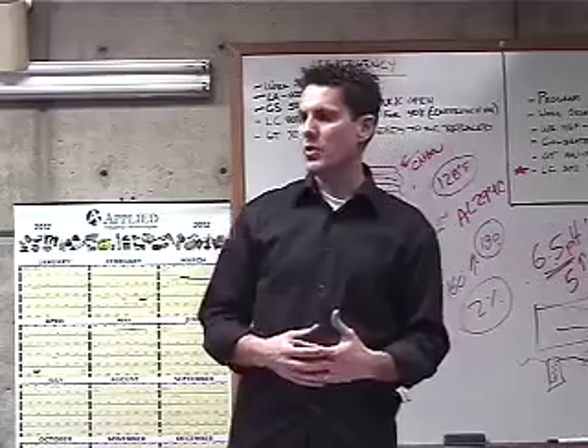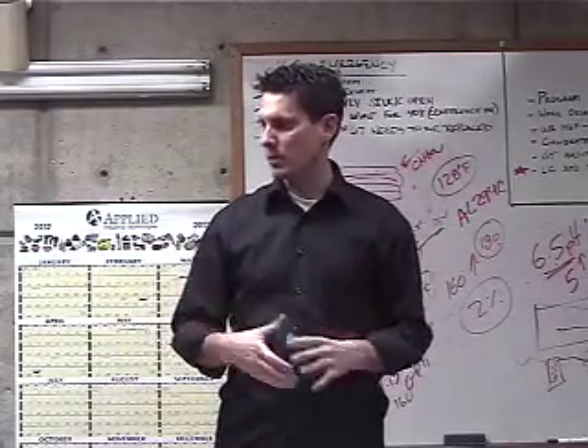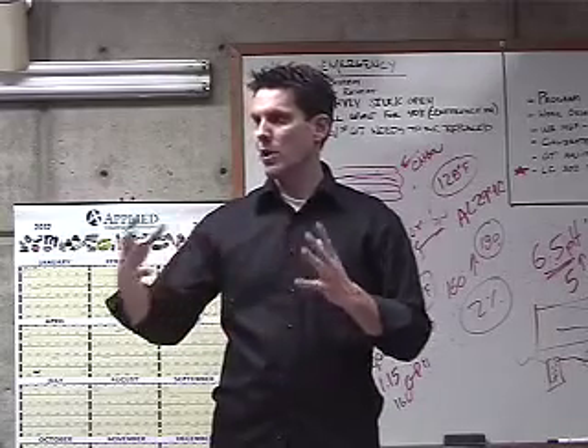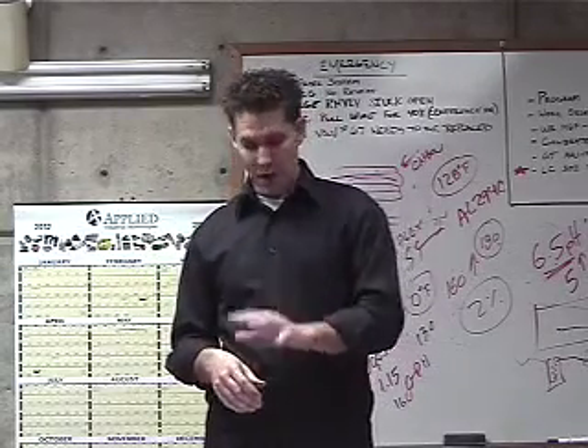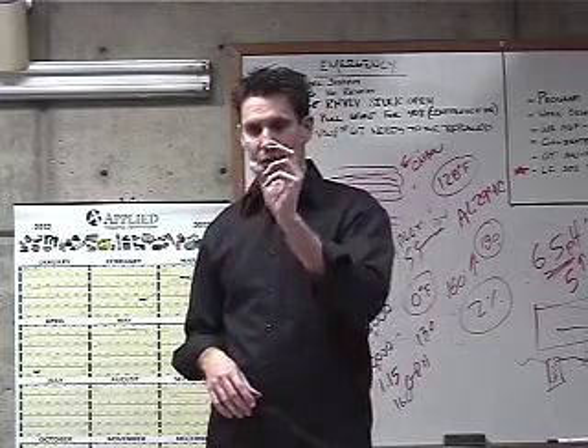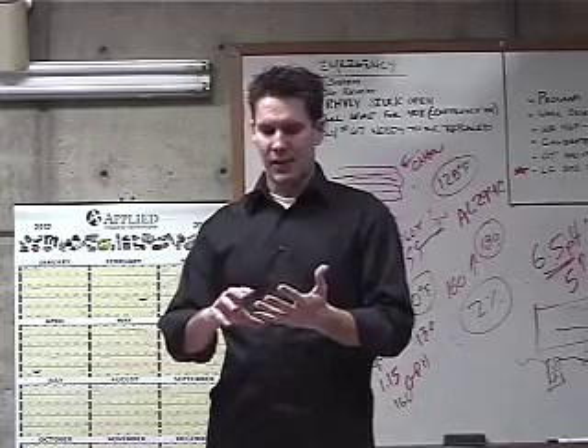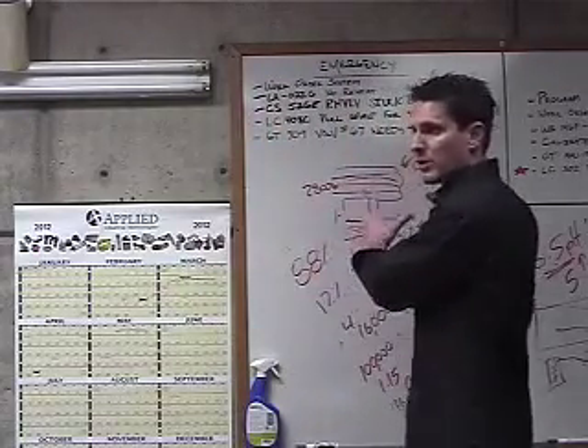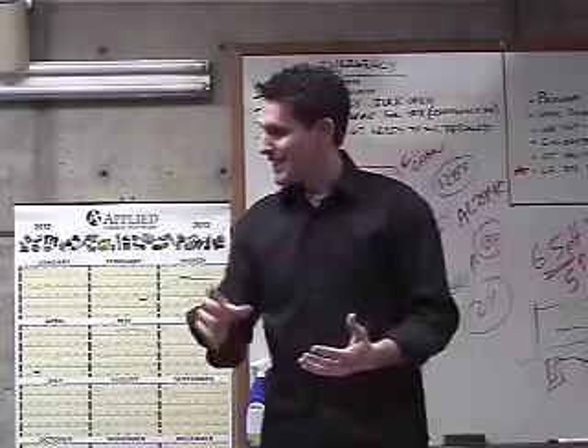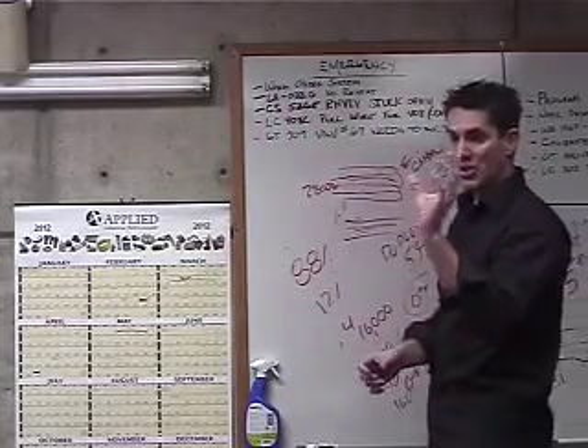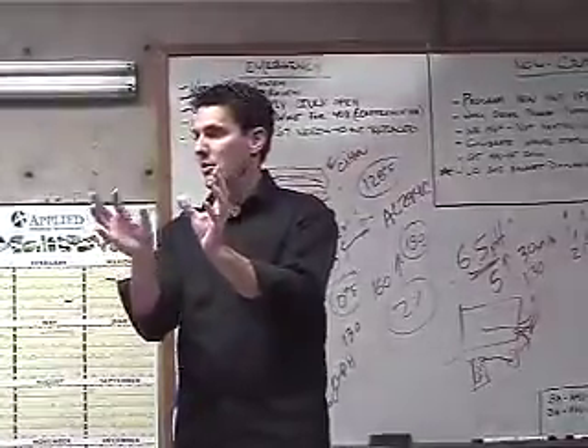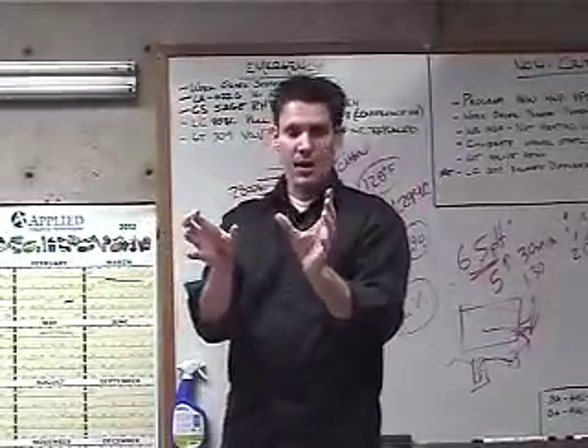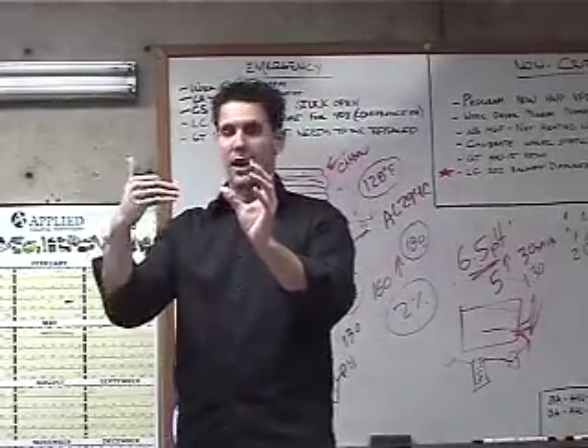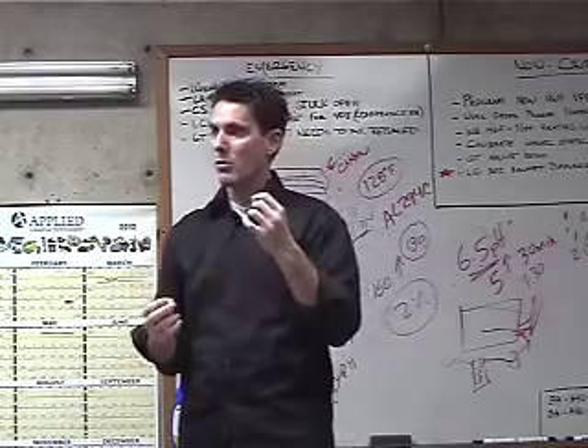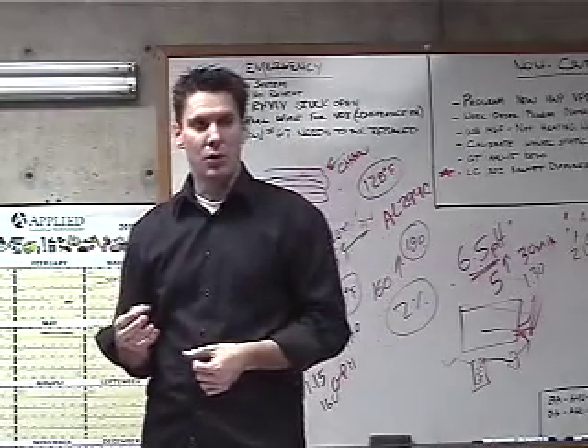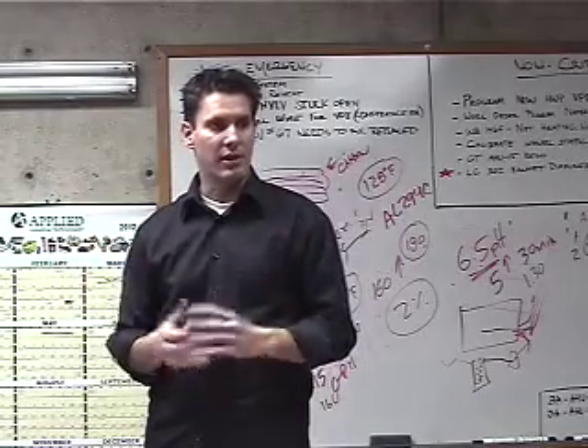If these boilers operate outside of their normal operating range, again, we've set some of the operating range up, and we'll go over some of that. But if they start to operate outside of their normal operating range, one of the fastest things that you'll see, and we go over this in the actual maintenance of this thing, is you'll see the flame color change. We've set this, again, going back to what we just talked about. Again, this is important groundwork to this whole training. To get the proper combustion that we've talked about, to get that CH4 and the 2 molecules of oxygen, requires some tuning on our part when we start these things up. We have to make sure that we have enough excess air, enough oxygen molecules for this whole process of combustion to occur. What we do is we dial that into about an 8% CO2, which gives us about 10% excess air using the natural gas we have here.